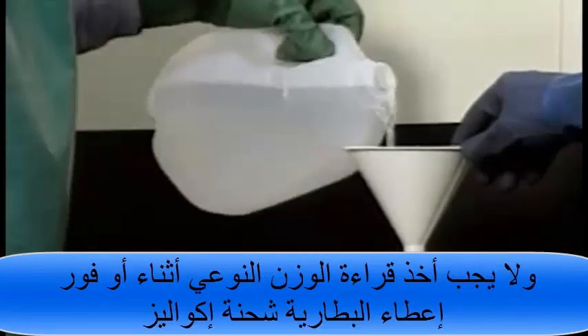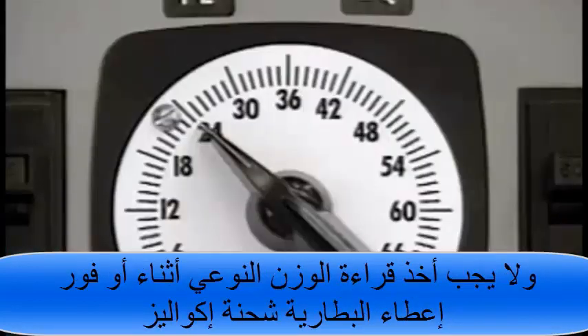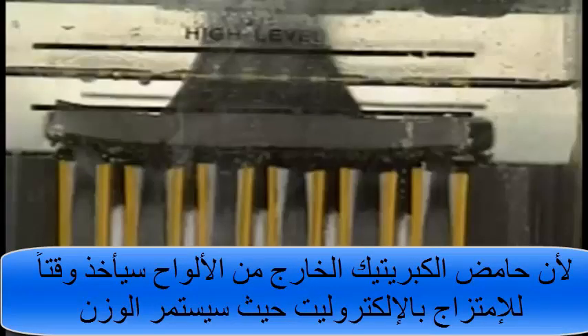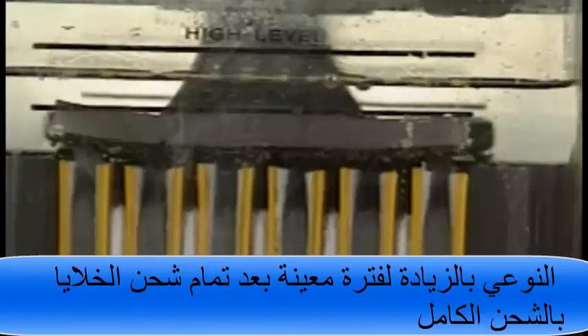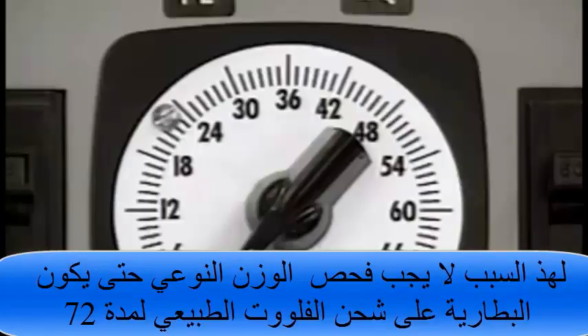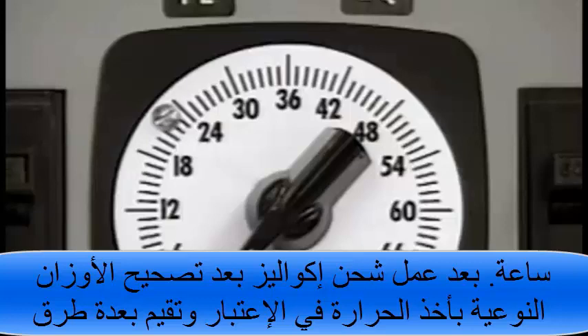In addition, specific gravity readings should not be taken during or immediately after a battery is given an equalizing charge. The reason is that it takes time for the sulfuric acid from the plates to mix with the electrolyte, so the specific gravity will continue to increase for a period of time after the cells have been fully charged. For this reason, specific gravity should not be checked until the battery has been on normal float charge for at least 72 hours after an equalizing charge.